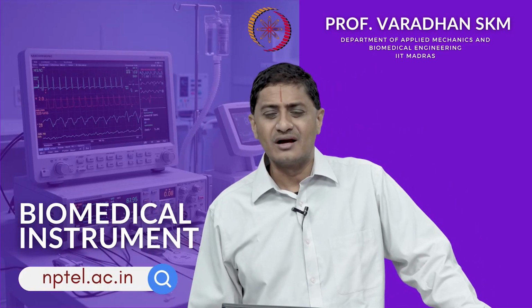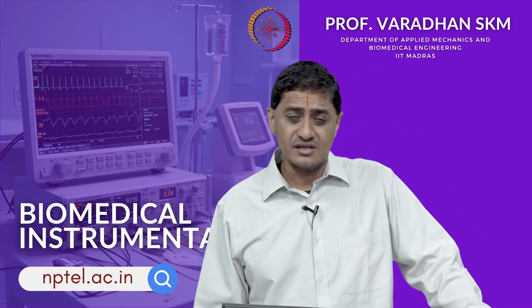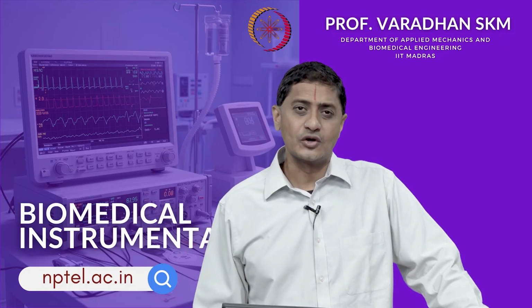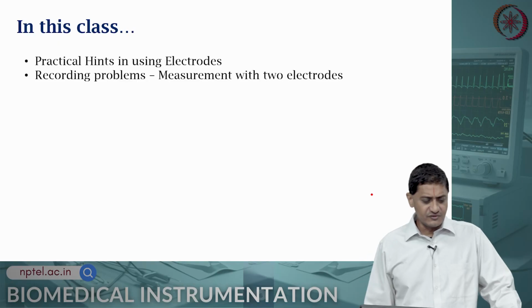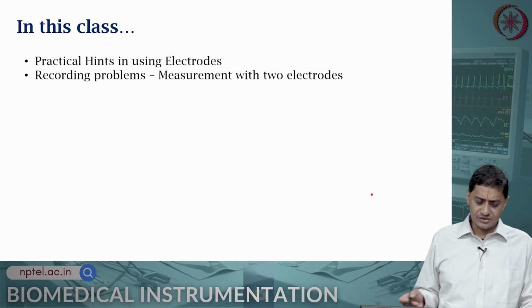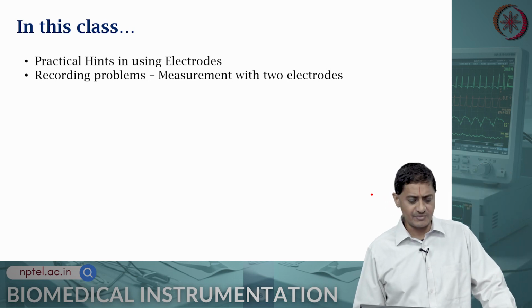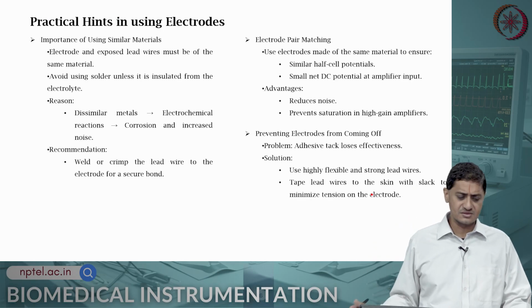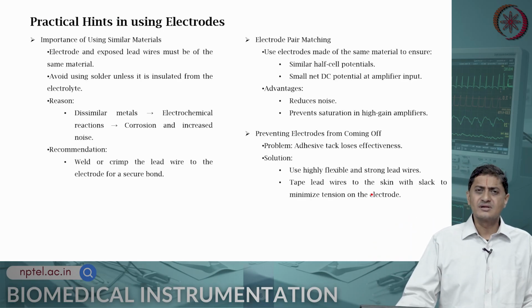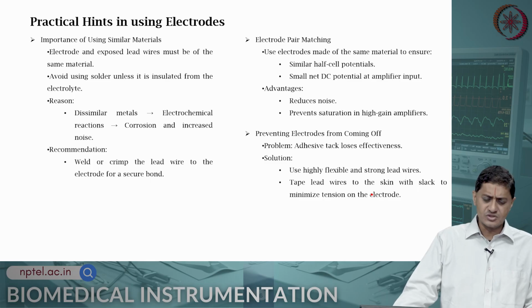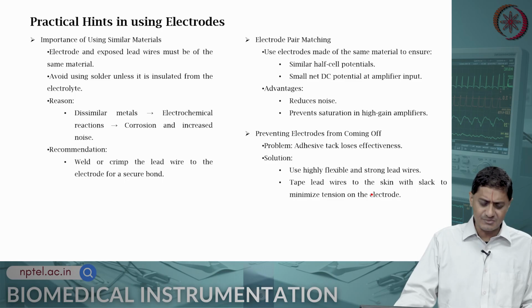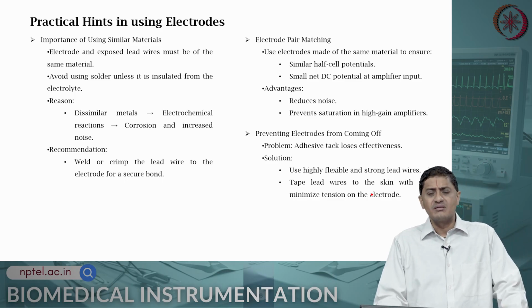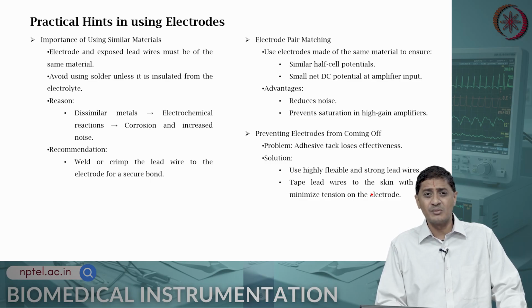So far we have been looking at electrode theory and we have looked at microelectrodes in the previous set of videos. In this video we will look at some practical hints in using electrodes and some recording problems that can happen in measurement with two electrodes. Some of the practical hints: one critical approach is to use the same metal. The electrode and the exposed lead wire must be of the same material. Why? Because otherwise there will be some electrochemical reaction that could happen, and corrosion and increased noise could happen.